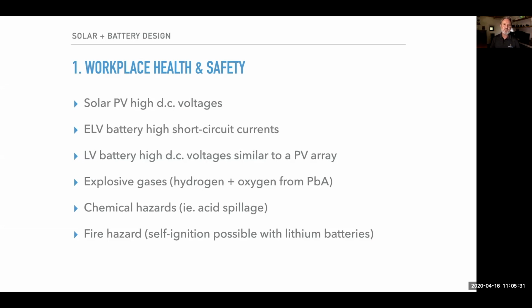Even at slightly less than 120 volts DC, there's still risks, particularly from burns or people with sensitive hearts. You can still damage internal tissue. At extra low voltage, now extra low voltage is starting to become a bit of a redundant term, the way our standards are moving towards the IEC definitions, but as it currently stands in AS/NZS 3000, extra low voltage sounds perfectly safe. Actually, it just means less than 120 volts DC. Now, if you've got a battery system operating in that range, it will still have an enormous amount of current potential. And so it's not necessarily electrocution that's the risk, or electric shock, but it's burns and possibly fire. So short circuits in ELV systems are a major risk too. So that's why it's very important to use insulated tools when working on ELV battery systems.